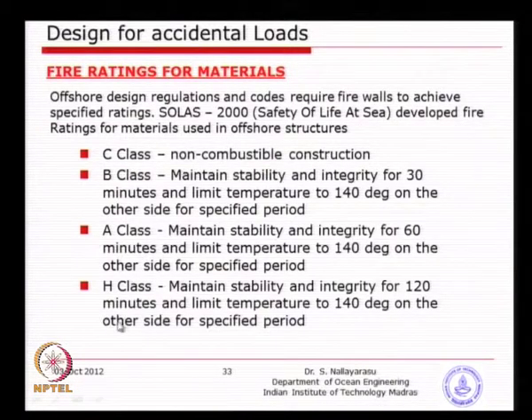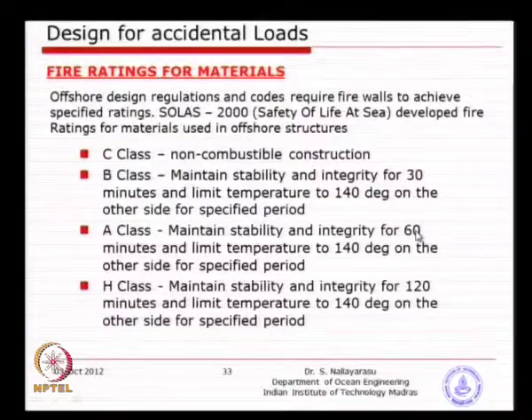The H class maintains stability and integrity for 2 hours and limits the temperature to 140 degrees C on the safe side of the wall. The A class barrier requires 1 hour and 140 degrees. In all three cases, the temperature must be brought below 140 degrees. The difference is only the time duration — H class for 2 hours, A class for 1 hour, B class for half an hour. When you design a firewall, if you are given an A class design, you must maintain structural stability for 1 hour and limit the temperature to 140 degrees.